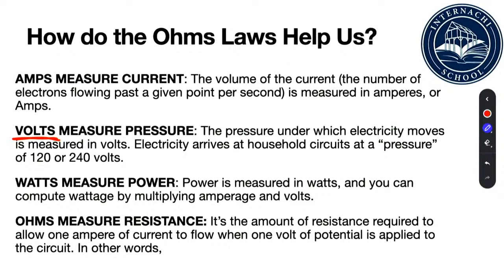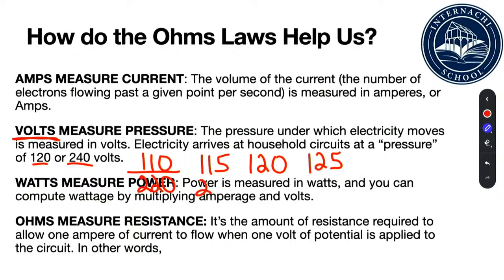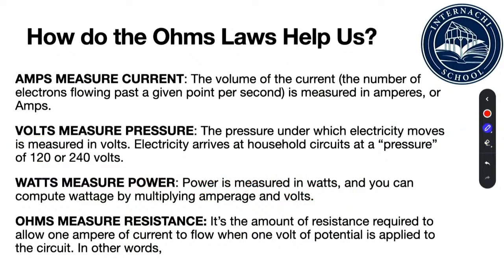The little trick on these things is using the numbers, going back to the slide beforehand, saying the right terms. I don't really care if you say 110, 115, 120, or what you'll see in code books, 125. What I do care about is that when we're talking about a single phase 120/240 system, you double these numbers. So if you say 110, then you're going to say 110, 220. You're going to say 115, 230, 120, 240, or 125, 250. We should be consistent in using the proper terms. But as far as measuring the voltage itself, that's just not something we do.